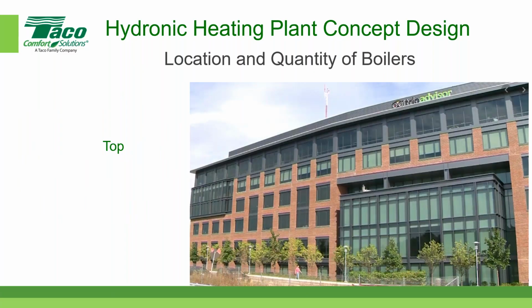All right. So where do you want to put your boiler plant? Well, you could put it at the top of the building. Usually if it goes at the top of the building, it's a penthouse type of arrangement, and there are lots of benefits to putting the heating plant at the top. But one of the drawbacks, again, is fuel, because you have to store it. Usually you're limited to the day tank size, relatively small storage at the boiler itself, and then you'd have to have a fuel oil transfer system. But you have a relatively small length of flue for your boiler system.